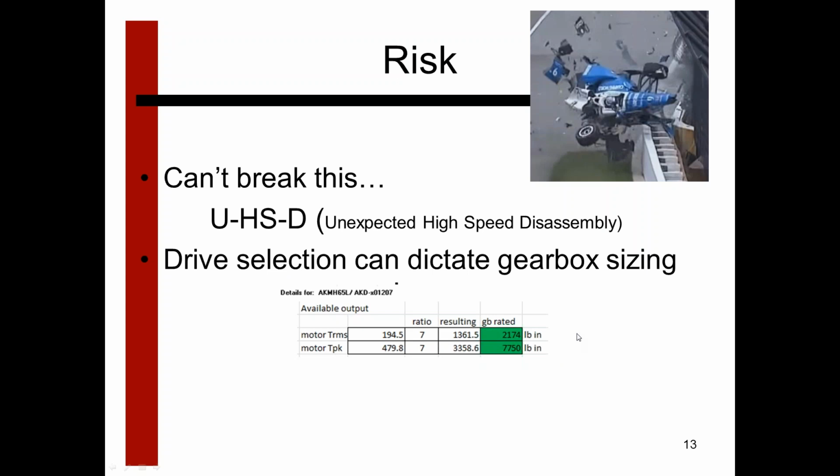There's been times when I've had an application where I did not need full torque rating out of a particular motor. I picked the motor based on other reasons, probably continuous torque, but the motor nameplate may have had much more torque available. For example, if you look at a motor nameplate and it says 35 inch-pounds continuous torque, 150 inch-pounds peak torque, just because you're looking at that nameplate on that motor, that does not mean that is what you are getting out of that motor. It goes back to what drive is running the motor, what's the peak current output of the drive. Now, if that is less than what the peak current rating was for the motor, which oftentimes is perfectly fine, if your application didn't need that peak torque out of the motor, now your limit is based on the drive output.